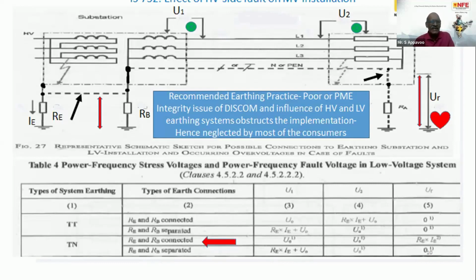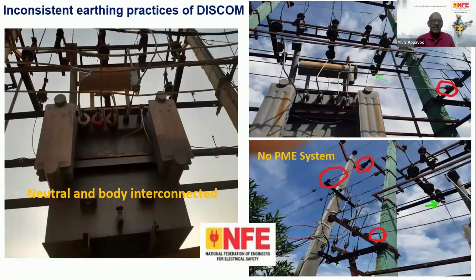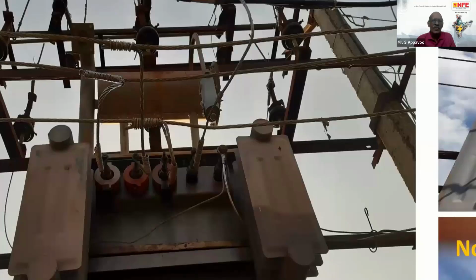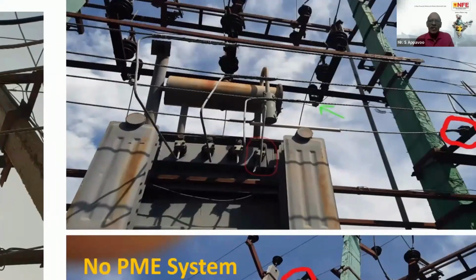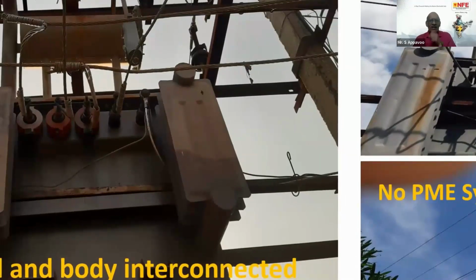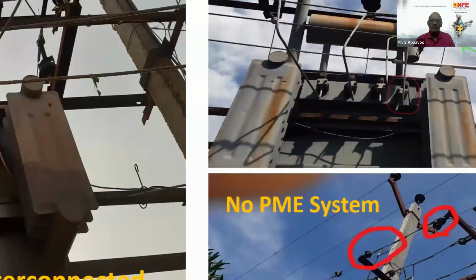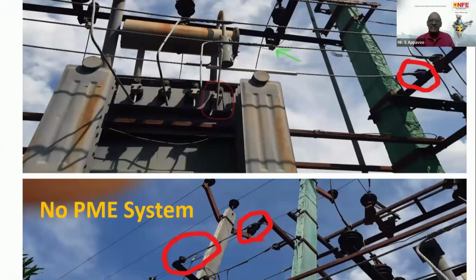Suppose it is separated, that is the type of earthing connection. If it is separated, then you will be safe. But can we separate? Again, separation will cause damage to the supplier equipment and to the supplier personnel also. So they will connect it. Unfortunately, we have a system where this is not being observed. For example, this is one distribution transformer where you can see the neutral is connected to the structure. By the same distribution company, the neutral is well protected. Here it is a TN-C system. Here it is a TN-S system. Sorry, here it is isolated. There is no earth connection.